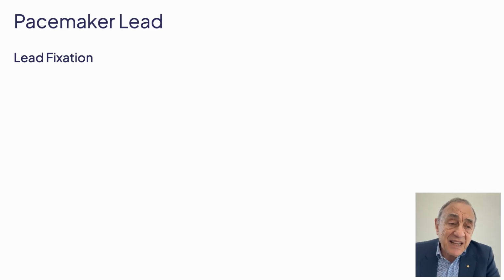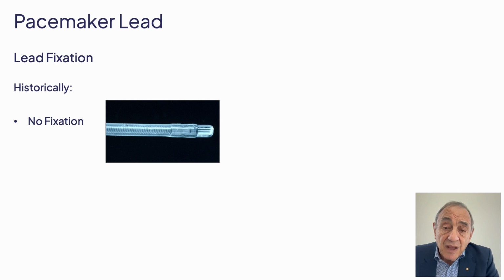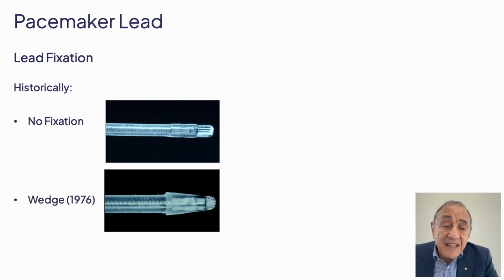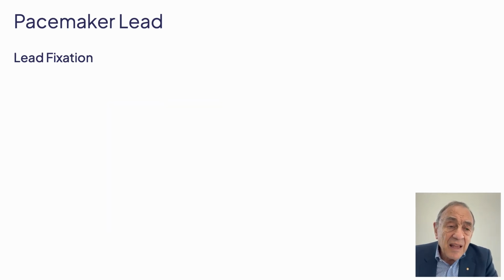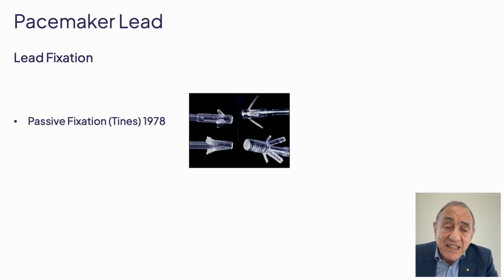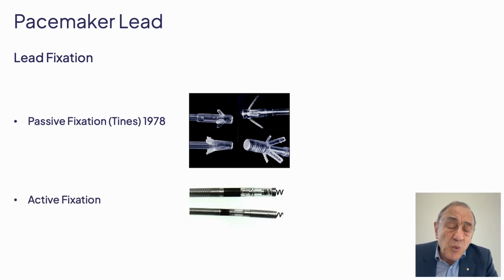What about lead fixation? Historically, there was no fixation. A wedge was then produced, and this resulted in marked improvements as these wedges were caught in between and underneath the trabeculae in the heart. We then went on to passive fixation, as you can see here, of all companies. Active fixation was available at this time, but rarely used because almost universally all these leads went on to have a high threshold exit block.